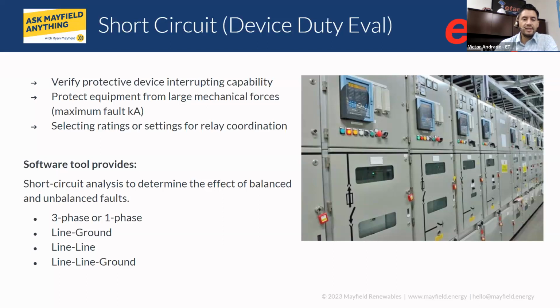So when you're doing a short circuit study, the software will automatically compare the calculated fault versus the interrupting rating of the equipment. So potentially making sure that the equipment is properly sized, right? And in the event of a fault, the equipment will function according to the manufacturer specifications. Because whether it's a line to ground fault or a line to line or a three-phase bolted fault, it's a huge release of energy. So we want to make sure that the gear and the protective equipment is properly rated. So that's the safety aspect of doing this particular study. So extremely important.